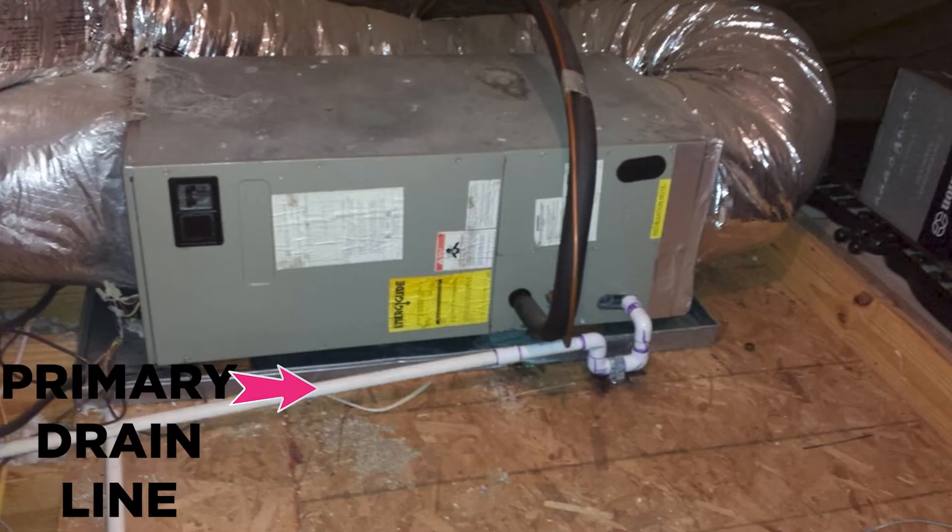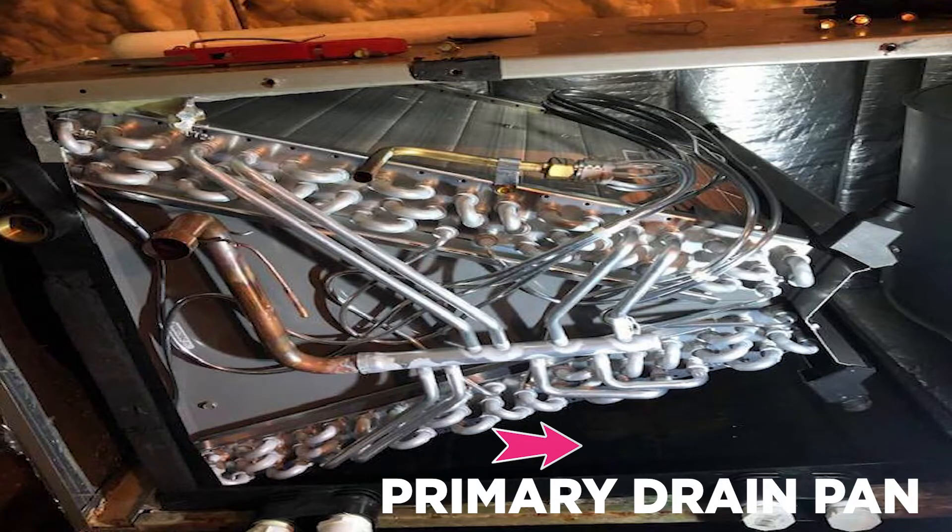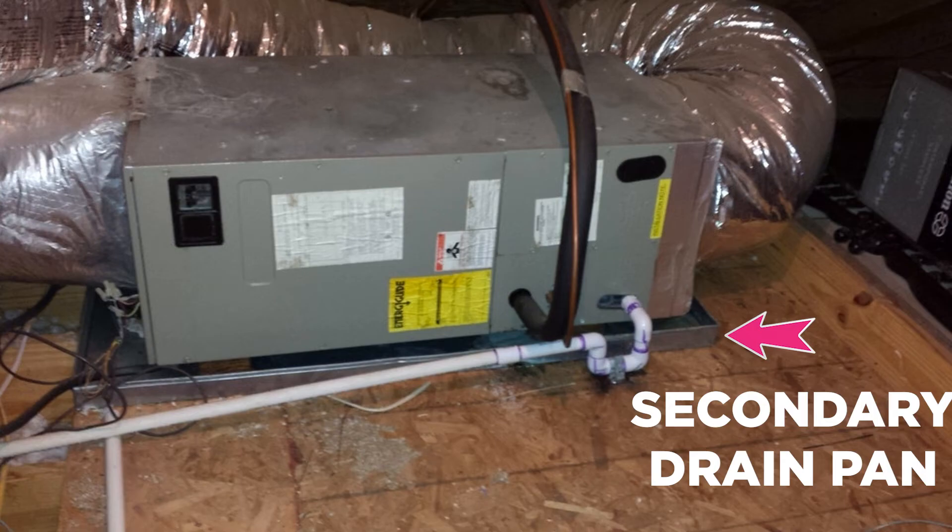If that primary drain line gets blocked up — and this is one of our most common calls — the primary drain line starts to get blocked up with a bunch of dirt, algae and snot in there. And the water, instead of leaving the house, now starts to build up in the primary drain pan. Some people even have a secondary drain pan in their attic, and that water starts to overflow into the secondary drain pan. Eventually it overflows onto your ceiling, and now you're talking about thousands of dollars to fix that.